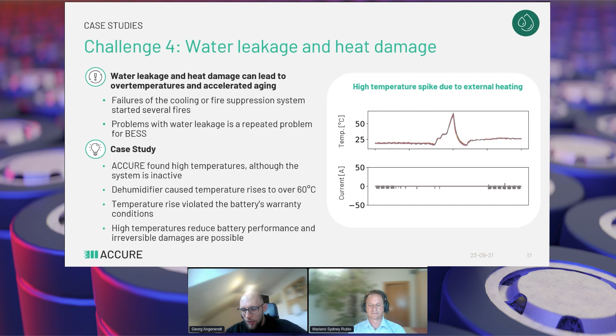What we found out is that the dehumidifier causes this temperature rise. They had a leakage or water leakage in their container, so the container was wet, and what they did is they tried to dry the water with the dehumidifier. But the dehumidifier causes the temperature at the battery system to rise over 60 degrees. Of course this is a big problem, because after such temperature rises, the battery warranty is already violated. These high temperatures can reduce battery performance and lead to irreversible damages. So it's not safe to run this battery.